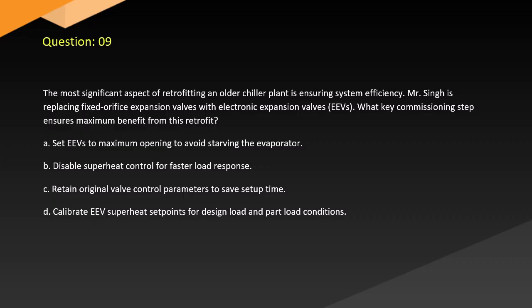Question 9. The most significant aspect of retrofitting an older chiller plant is ensuring system efficiency. Mr. Singh is replacing fixed orifice expansion valves with electronic expansion valves (EEVs). What key commissioning step ensures maximum benefit from this retrofit? A. Set EEVs to maximum opening to avoid starving the evaporator. B. Disable superheat control for faster load response. C. Retain original valve control parameters to save setup time. D. Calibrate EEV superheat set points for design, load, and part load conditions.